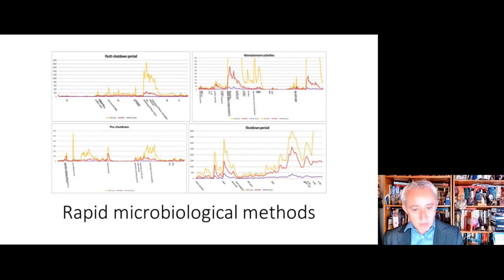With these charts, biological readings or bio-readings are in red, particle counts are in yellow. Here we've got clean room in different states in relation to different activities in a facility. We've got normal operating conditions before a shutdown, activity during a shutdown, bringing clean rooms fully back online but still undergoing cleaning and disinfection and the disruption that causes and the time required for that to settle down, and then the clean room back in use post-reinstatement. This type of information can help us understand what is normal in terms of biological activity. It can help us understand the impact of people in an area and equipment movements. It helps us understand what happens when an area is declassified, the impact of cleaning, and how long it takes to recover before it could be potentially considered for GMP activity. You can also apply this technology into interfaces around airlocks or in changing rooms to help establish the maximum number of people permitted or the recovery time after use.